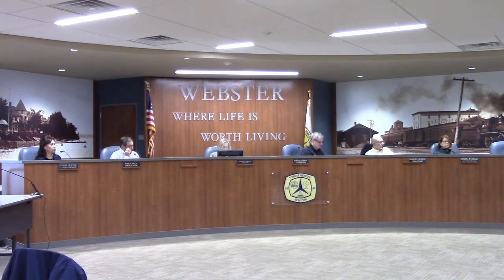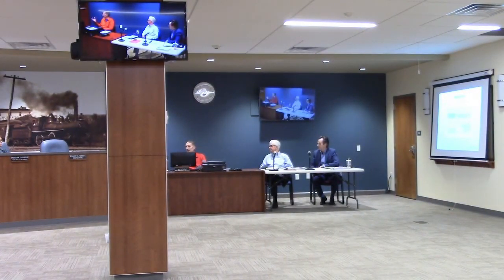The supervisor had mentioned it, okay, we got another pump station. I will say, due to the help of our budget, a lot of our smaller pump stations, we've absorbed those upgrades and modernizations into our budget. This year we have the Shoecraft pump station, which will receive new pumps and a new control panel. Actually, the guys started working on some of that this week. Our HAPA pump station, right outside of a senior living facility, is a very problem pump station. We spent a lot of time there cleaning bags and diapers and things of the sort. We were able to purchase 2 new pumps for $10,000.